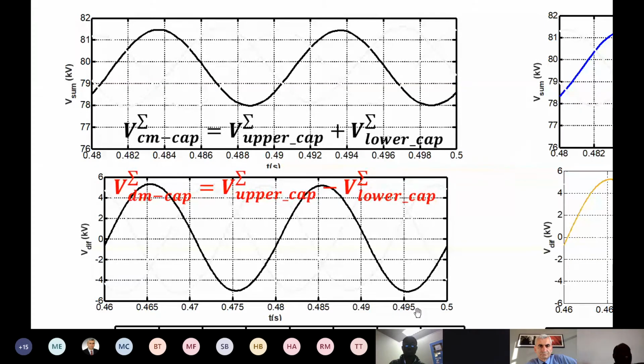And you can see here in the MMC in general, if we add the capacitor voltage sum, if you add all the capacitor voltages in the upper arm plus all the capacitor voltages in the lower arm, you add them together, it gives you a DC component. On top of it, there is second order harmonics, while if you subtract the capacitor voltage sum of the lower arm from that of the upper arm, you will get the fundamental component. So this is the component that drives that second order harmonics in the arm of the MMC. This is the point I want to communicate from this one here.